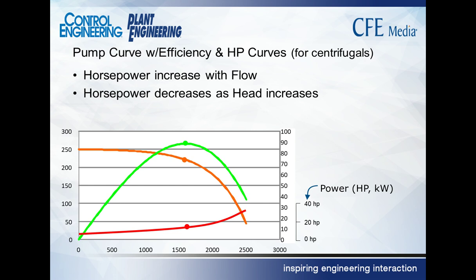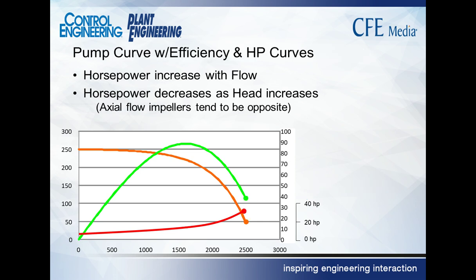So if you look at a pump curve, what do we have? We have flow, we have head, we have efficiency. So if we have those 3 for any point on the curve, we can use that formula and say, hey, I've got power as well, so now we've added the power. These are the 4 parameters that are displayed on virtually any pump curve that you'll run across: flow, head, efficiency, and power.